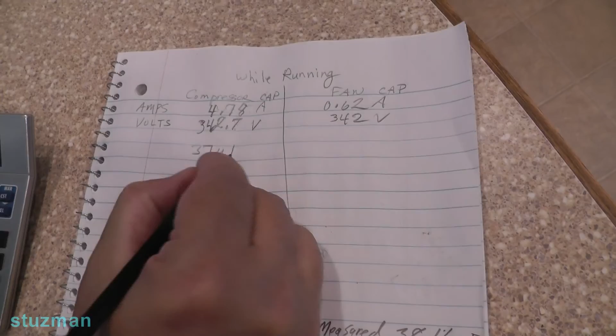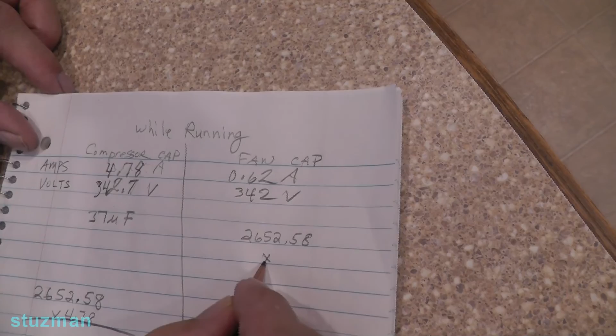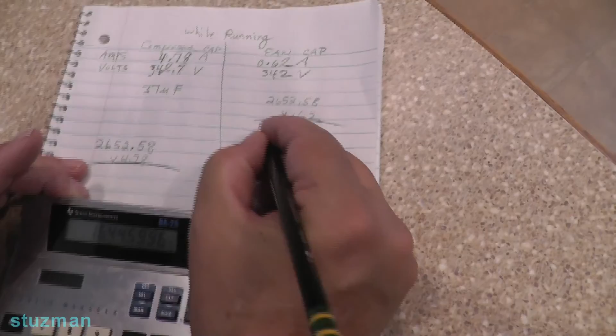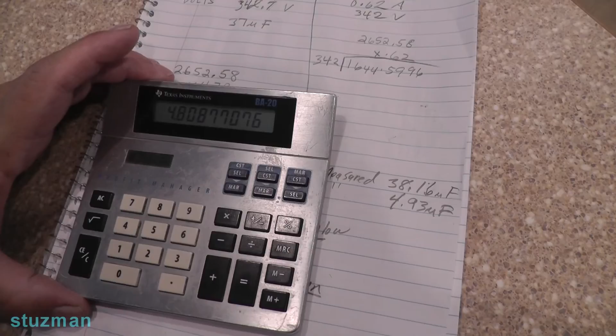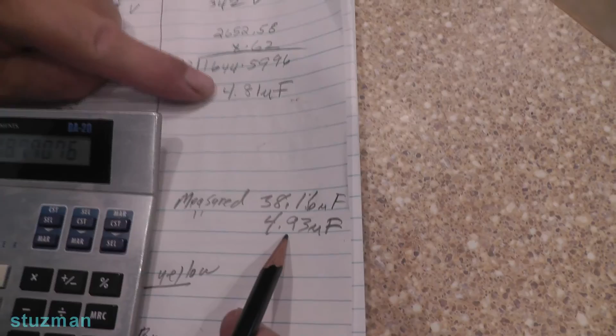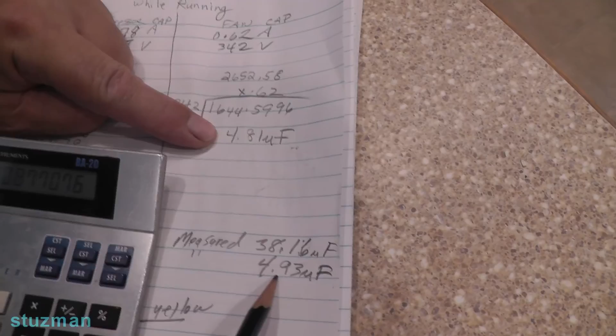Now let's take a look over here at our fan capacitor. We're still going to use the same number, 2652.58. We're going to multiply it times our amperage, 0.62. We do that and let's see what we get. 2652.58 times 0.62 is going to be equal to, and let's just write it out, 1644.5996. Now we're going to divide that number by our volts, which is 342. So I'm going to divide that by 342 equals, and you see we get 4.81. I'm going to round it off to 4.81 microfarads. And if we look down here, you can see that we had 4.93 microfarads. So we're only 1/10 of a microfarad off.